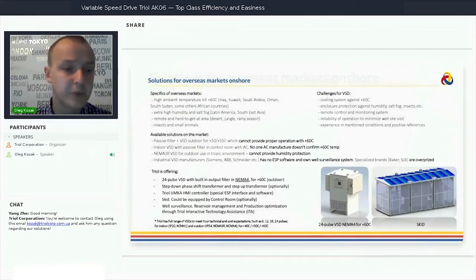This drive doesn't need any input filter because the 24 pulse design reduces harmonics in accordance with THD requirements. You only need a step down phase shift transformer and a step up transformer, which could be supplied by your own from Chinese cost effective suppliers.